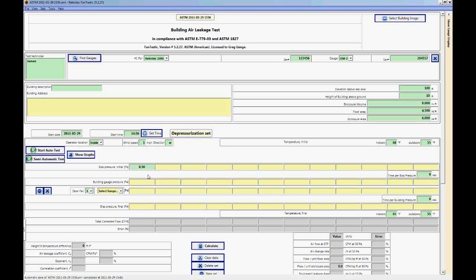And ASTM only requires that you take one bias pressure reading. So ASTM also requires that you take readings from between 10 and 60 pascals and anywhere between 5 readings and 12. As you can see there are 12 spaces here.